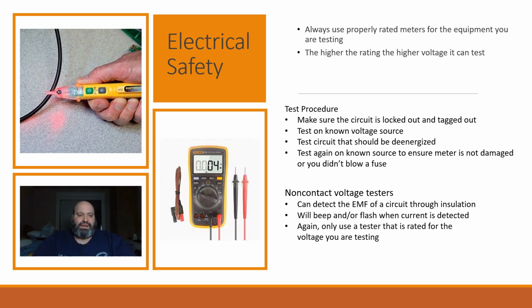So that said, before we work in a circuit, and after it's locked out and tagged out, we want to really make sure that it is in fact off. Again, using our properly rated meter for the equipment we're testing, we're going to test the voltage on a known source of power, so another circuit that we know is energized. We're then going to test our de-energized circuit and verify that we don't have any power flowing. We're going to go back and test that known source again because we want to make sure that our meter isn't faulty. So we want to follow this procedure when we're testing a circuit to verify that power is out.